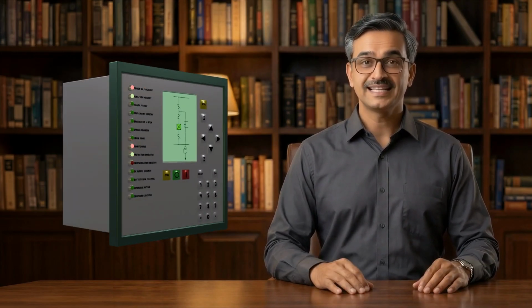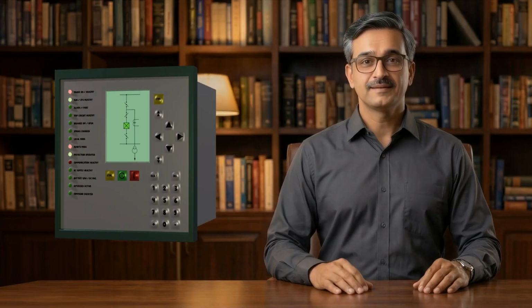The BCU acts as an interface between the substation's hardwired equipment and the HMI, the human-machine interface, in the control room. It receives current and voltage signals, transduced analog signals, and open/close contact status from the equipment. It processes these signals and sends them using the IEC 61850 communication standard, the universal language of modern substations.